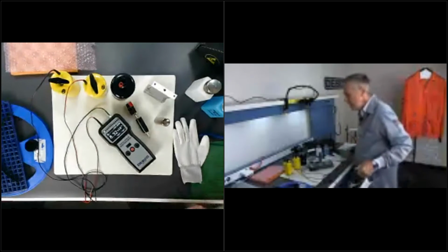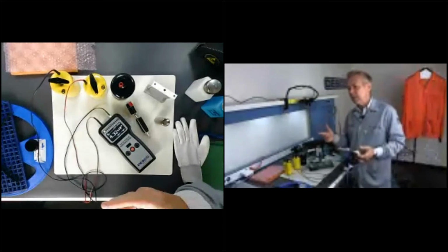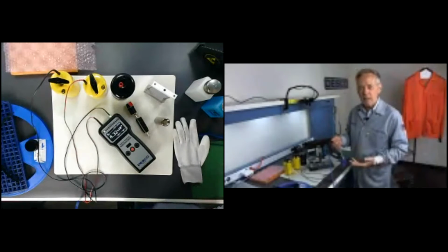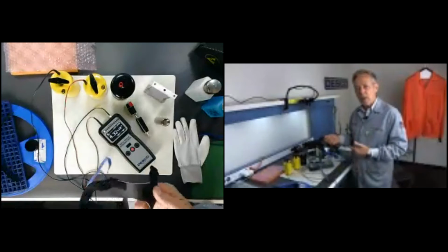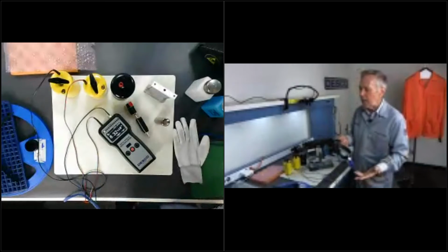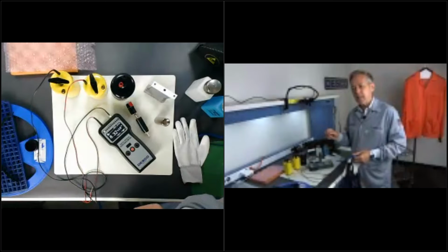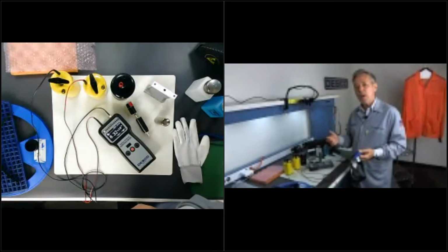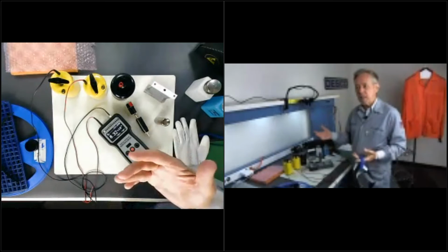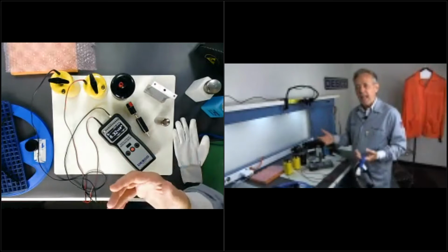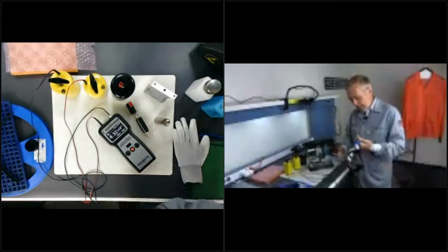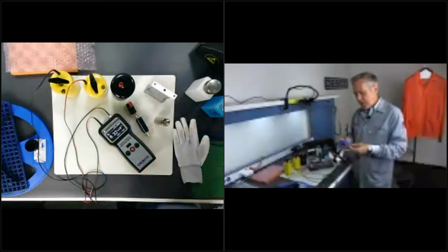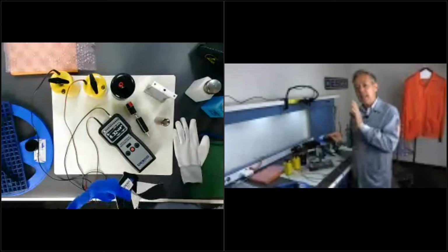Okay, so we often get a call and people say, everybody's failing on our foot grounder tester. They're wearing ESD shoes or they're wearing foot grounders or whatever. We're all failing high, or some people are failing high. And we typically get these questions as the temperature drops and humidity drops. And oftentimes early in the morning, you get into work, 6:30 in the morning, 7 o'clock, you haven't started sweating. And if you're not sweating, you're not making good contact with the tab of your foot grounder.